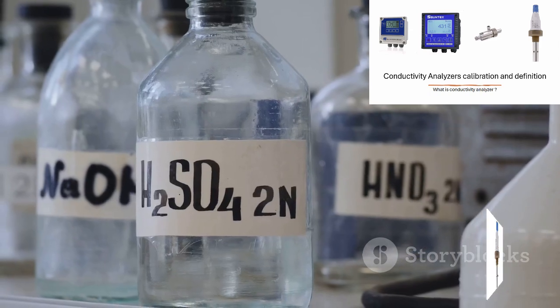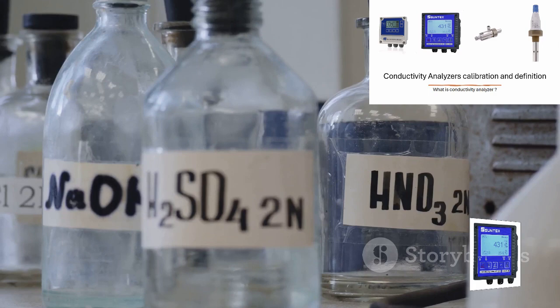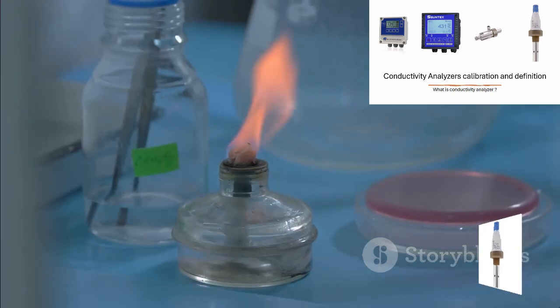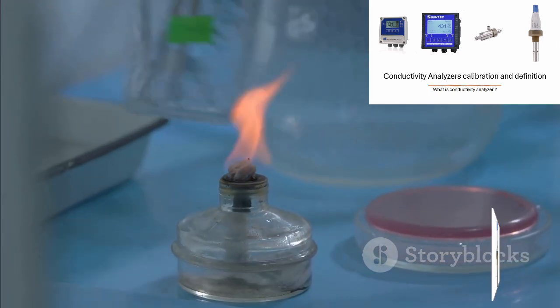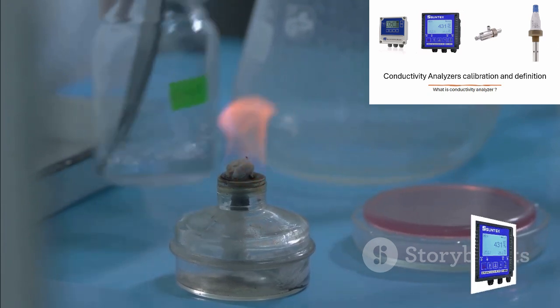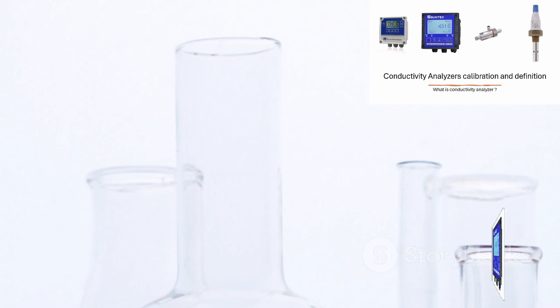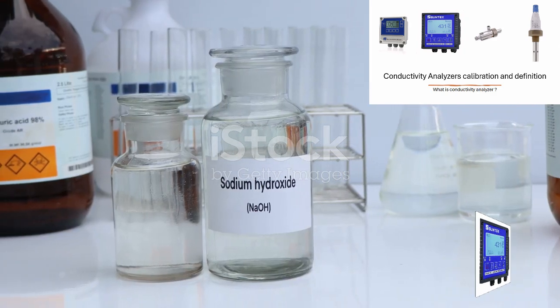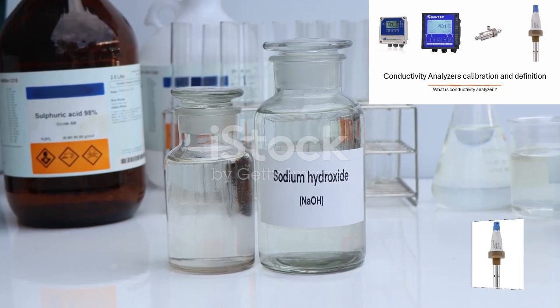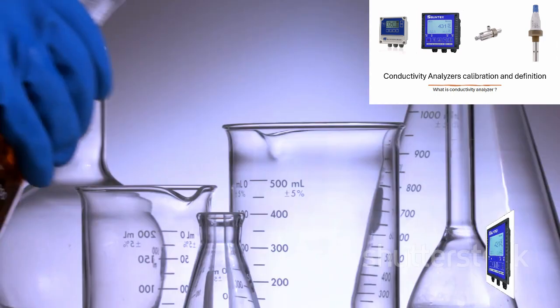You'll also need at least one, but preferably two, conductivity standard solutions. These are your reference points. They are special liquids that have a very precise, known conductivity value printed right on the bottle. Using a standard that is close to the conductivity you expect to measure in your samples will give you the best results. Don't forget the beakers.